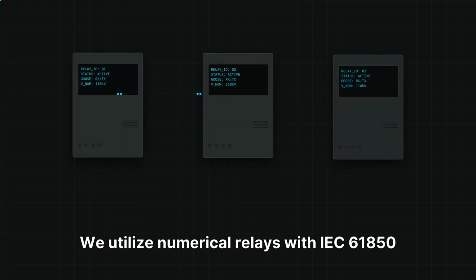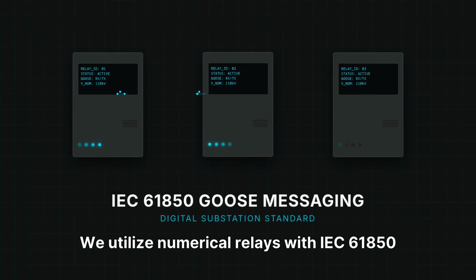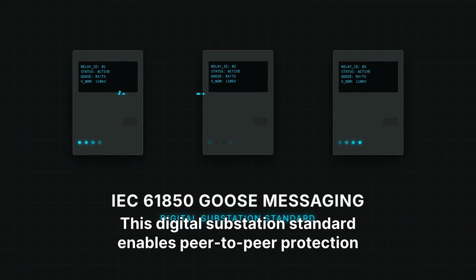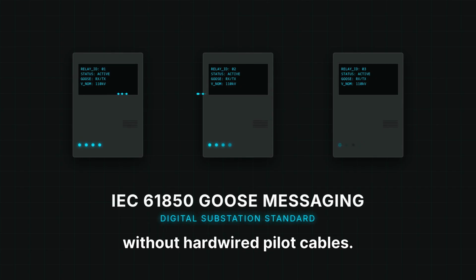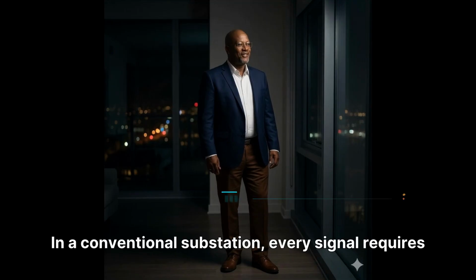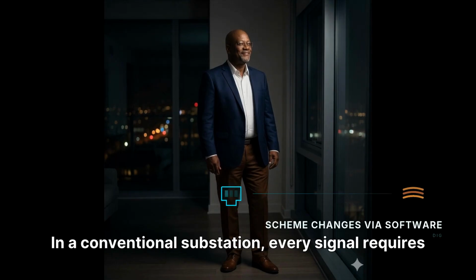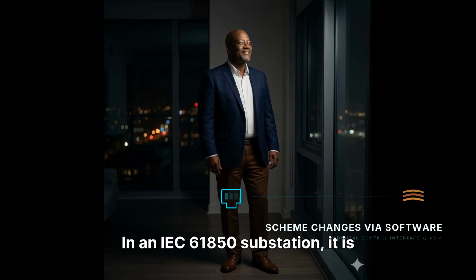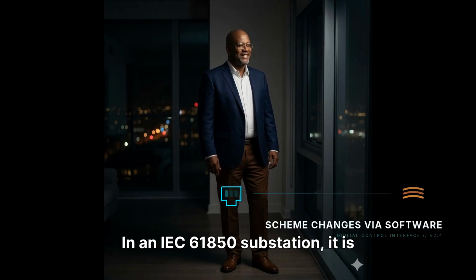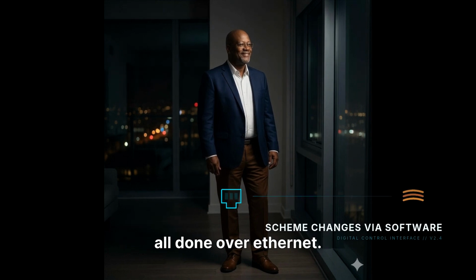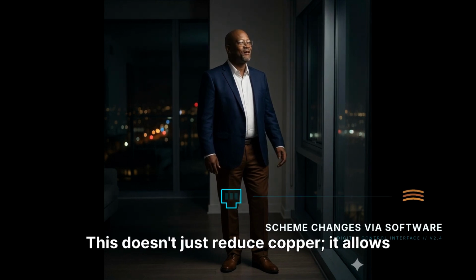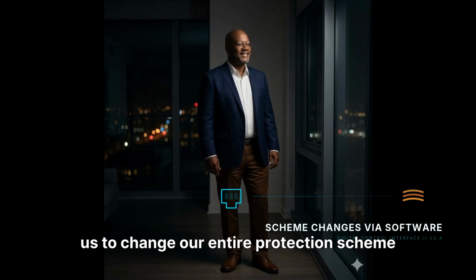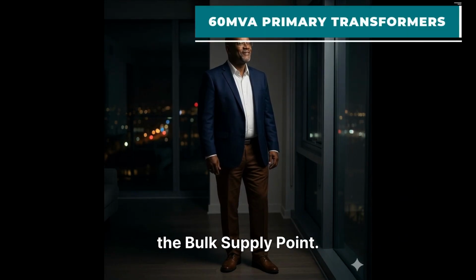We utilize numerical relays with IEC 61850 GOOSE messaging. This digital substation standard enables peer-to-peer protection without hardwired pilot cables. In a conventional substation, every signal requires a physical copper cable. In an IEC 61850 substation, it is all done over Ethernet. This doesn't just reduce copper, it allows us to change our entire protection scheme through software configuration. Now, let's look at the giants of the bulk supply point.